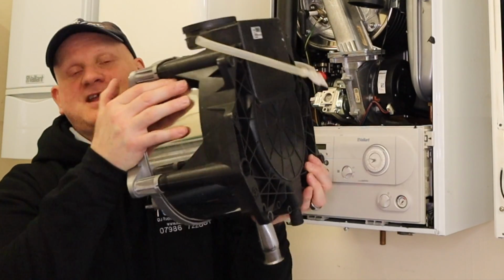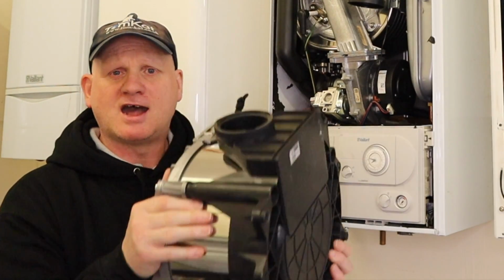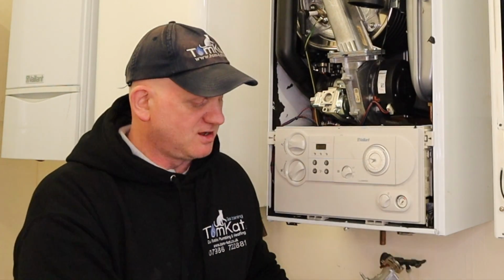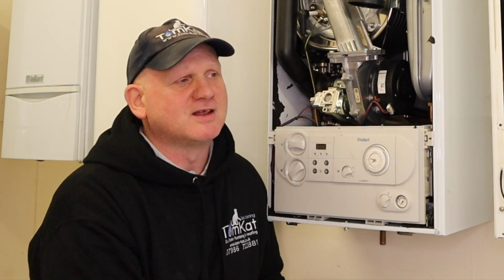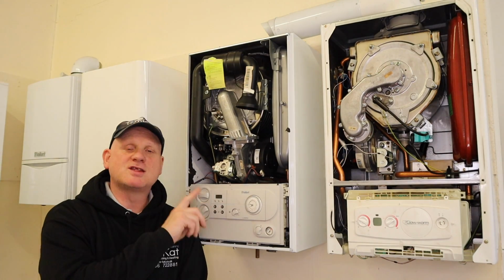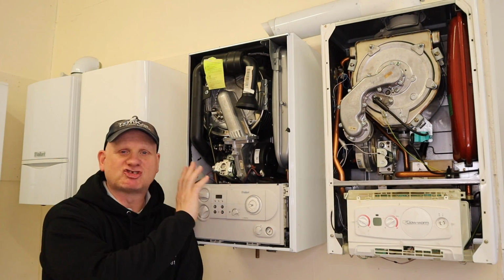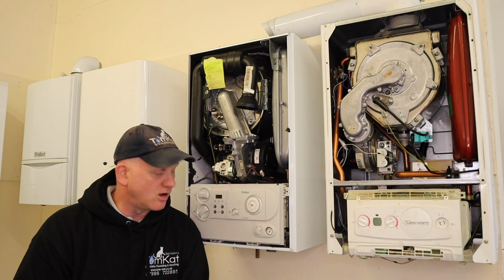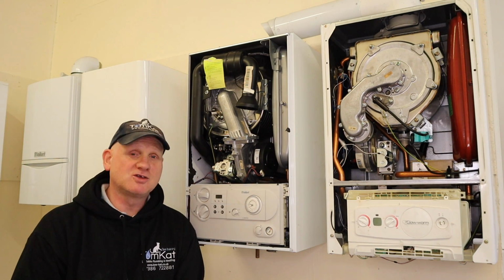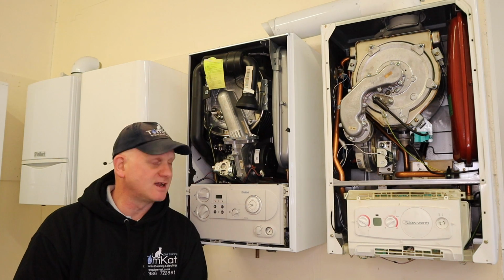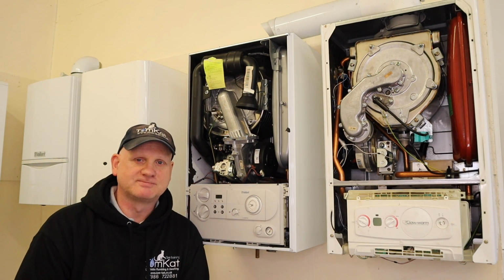While an aluminium heat exchanger is a lot lighter than these stainless steel ones, and a lot cheaper to manufacture, the properties of stainless steel are far superior to those of the aluminium heat exchanger, and it is less likely to corrode than the aluminium one if your pH levels aren't perfect like they should be. Stainless steel is known to be one of the most durable and strongest metals we have on our planet. So that's another good reason why manufacturers use stainless steel for a heat exchanger.